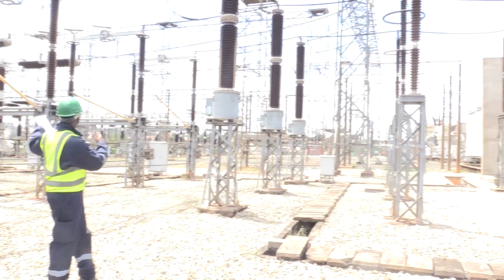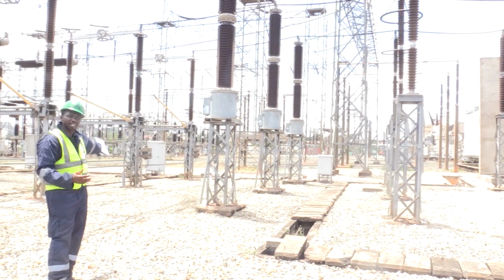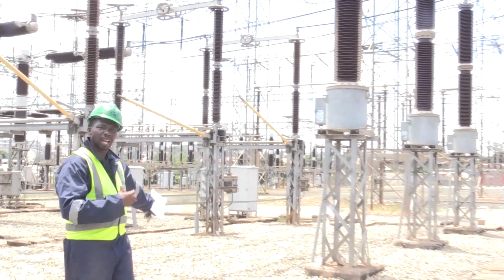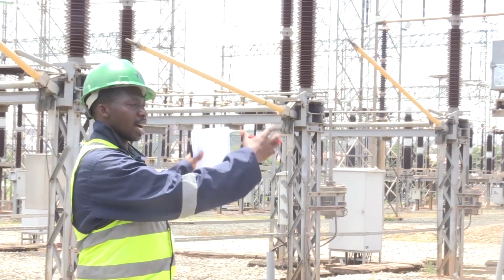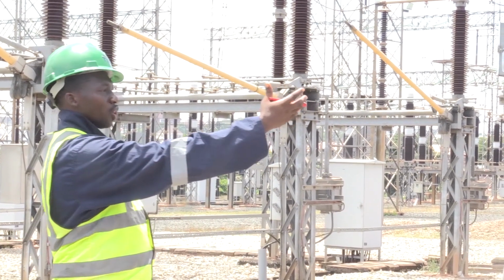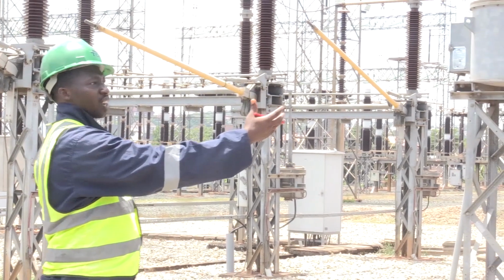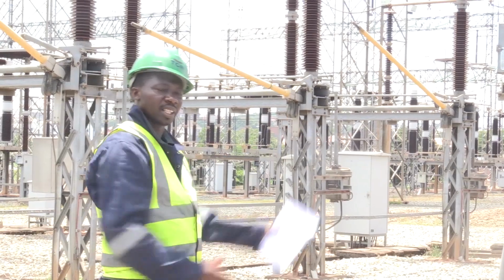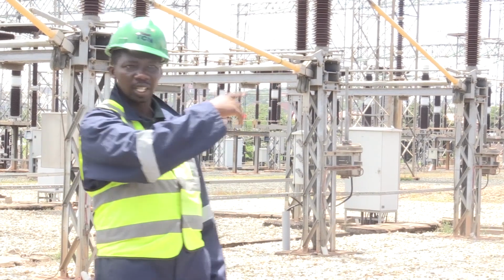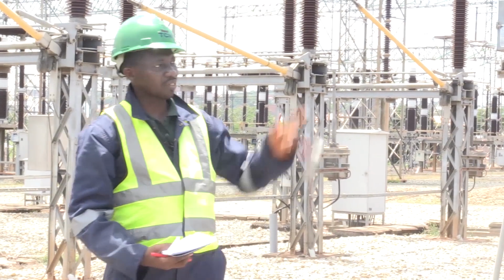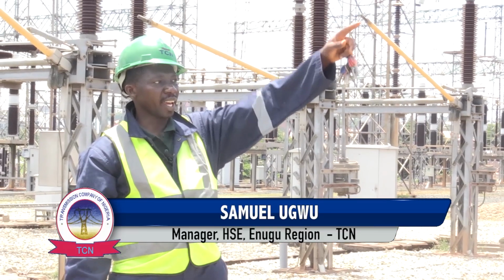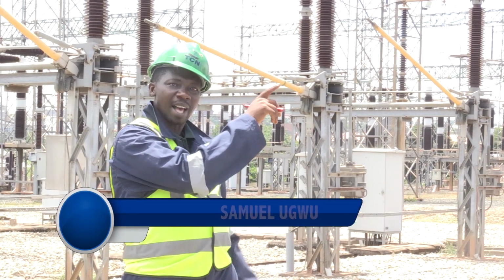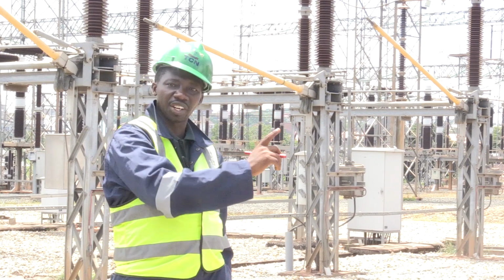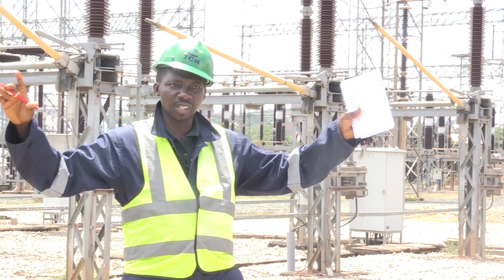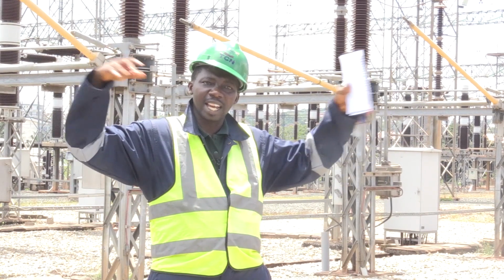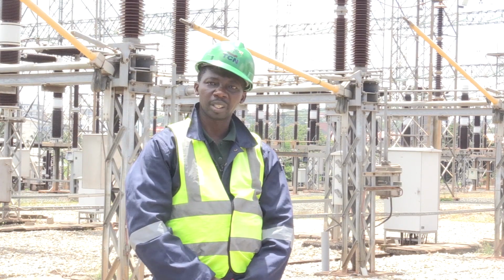In between we also have the CT for measurements and metering, which helps us with the accurate measurement and metering of the energy we are receiving here. It gets to the transformer, and when it hits the transformer, we are receiving 330 on the primary, and on the secondary we take out 132, which transverses down to the 132 bay into the transformers there, which will now take out 33 to the various substations and distribution stations, from where they can take it out to the public.